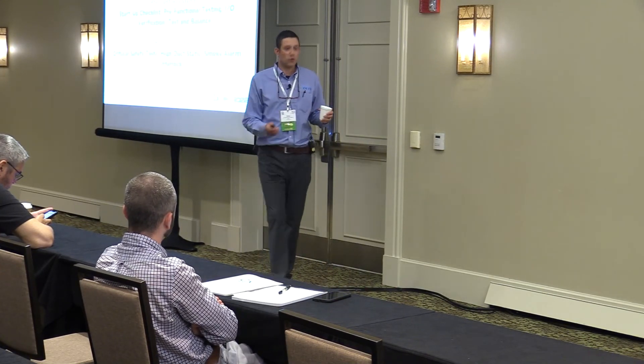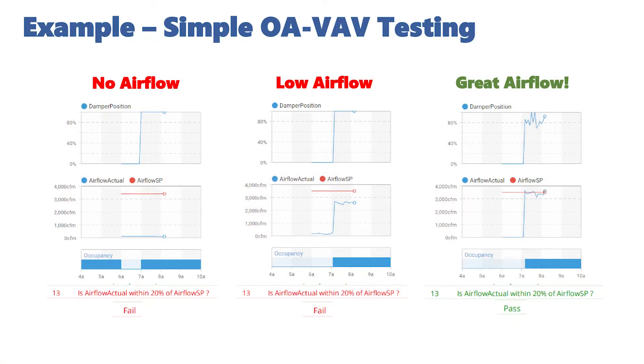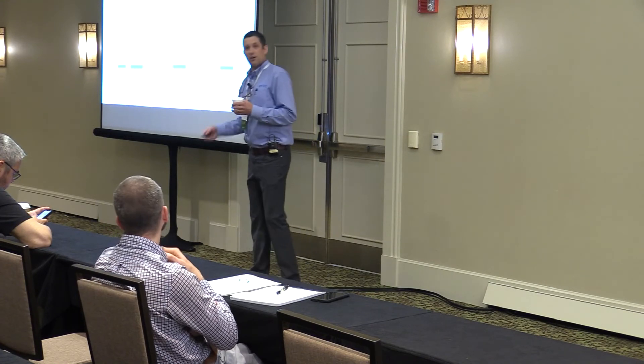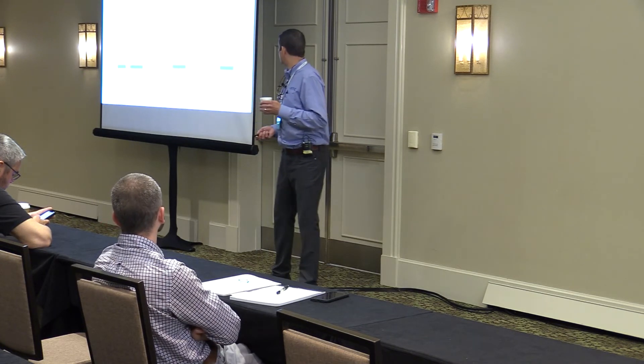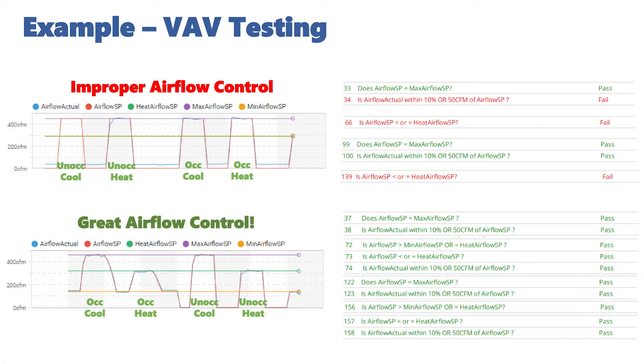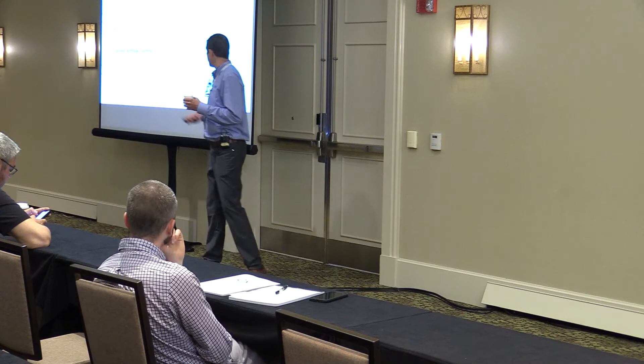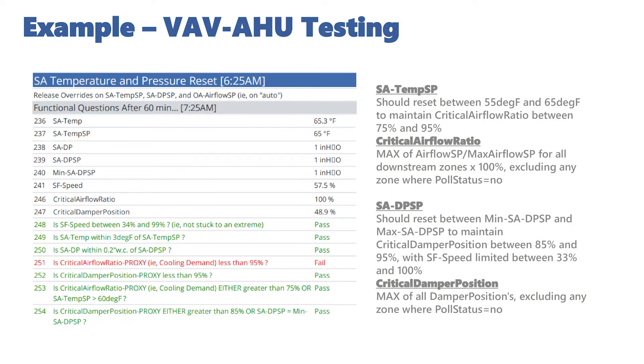Let's go through some examples. Here's a simple outdoor air VAV test. On the far left, when the building becomes occupied the outdoor air damper for the floor goes open but there's no airflow — automatically detected. The middle example is low airflow, automatically detected. The right example is a good one — the answer is positive in that case. Another example: on the top left the airflow was completely wrong when we first did the testing, and on the bottom left, after the contractor resolved and did proper programming, the airflow correctly shows what it should be doing in each mode — occupied and unoccupied, cooling and heating.